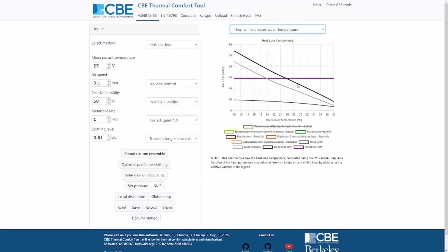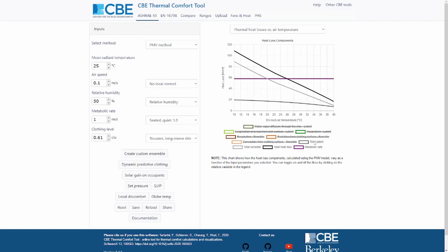You can also visualize the thermal heat losses versus the air temperature. These are the heat losses and heat gains calculated with the PMV model. You can visualize them here and toggle on and off different factors: total latent heat, total sensible heat, total heat losses, and metabolic rate. Where the total heat losses meet the metabolic rate, that's the comfort temperature — in this case roughly 26 degrees.